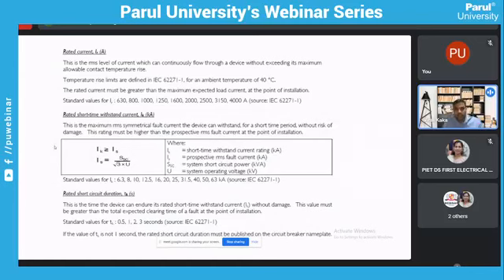Again, this is the same slide, so I'll quickly run through this one. Normally, the short circuit duration is 3 seconds as per practice, but you can still get 1, 2, or 0.5 seconds. That is not a conventional practice. You will always get a short circuit rating for the breakers of around 3 seconds.